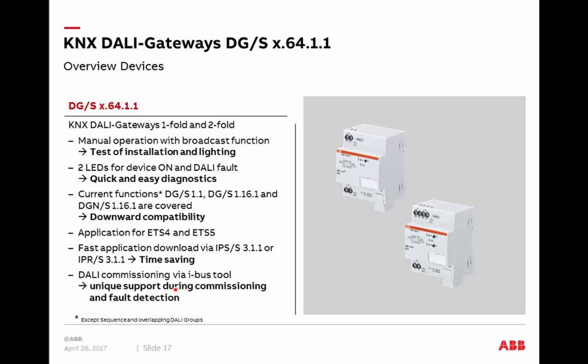The ABB i-bus Tool is of course integrated. For any DALI gateway to KNX from ABB, it is more or less a must to use — to parametrize the DALI part, including DALI addressing and DALI grouping. Compared to the existing devices, we have enhanced the situation with more functions inside the DALI tool and a better overview. It is a free-of-charge, unique tool from ABB for different KNX devices, especially for DALI gateways, providing all functions needed for smooth and fast commissioning.